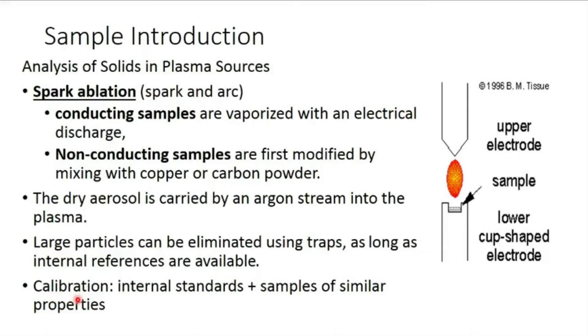Calibration means that if 10 units of sample is present, the signal given by the machine should correspond to that 10 units. To calibrate, a known quantity of analyte should be added to the machine and the signal adjusted accordingly. For example, if you are analyzing cadmium or iron, a sample containing a known quantity should be introduced, spark ablation carried out, and the signal should be proportionate to the sample taken.